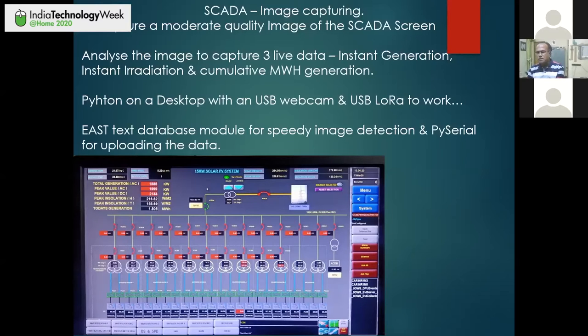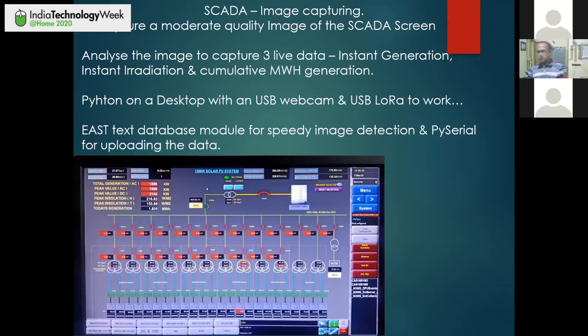The three data available are: instant generation in megawatt, solar insolation or irradiation available in watt per meter square, and the cumulative generation in megawatt-hour — on lines one, four, and six. These few data were essentially required by management for taking prompt decisions. So what we thought was to capture a moderate quality image of this SCADA screen and analyze the image to capture those three live data: instant generation, instant irradiation, and cumulative megawatt generation.